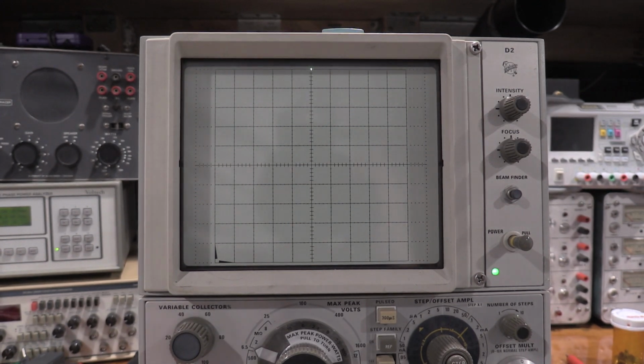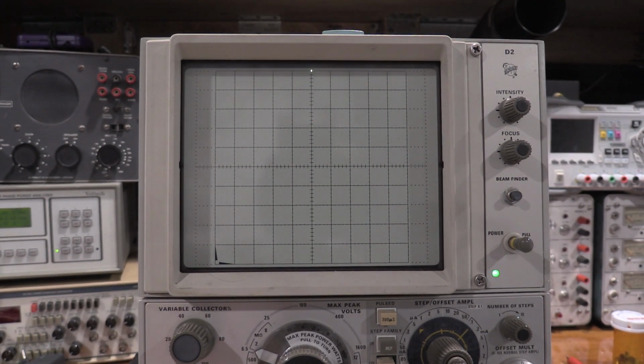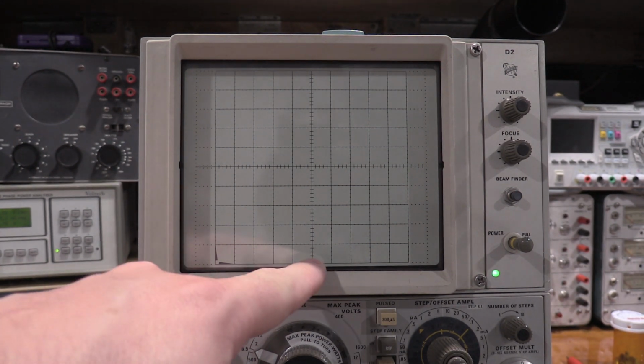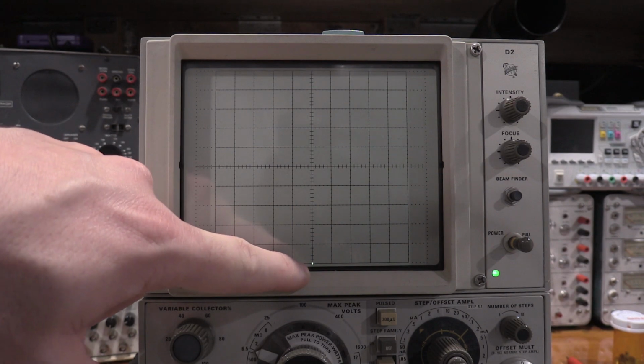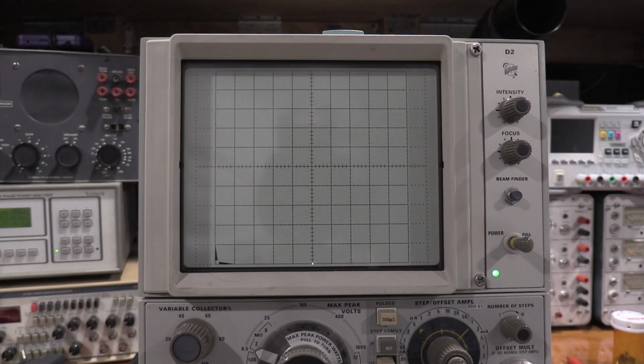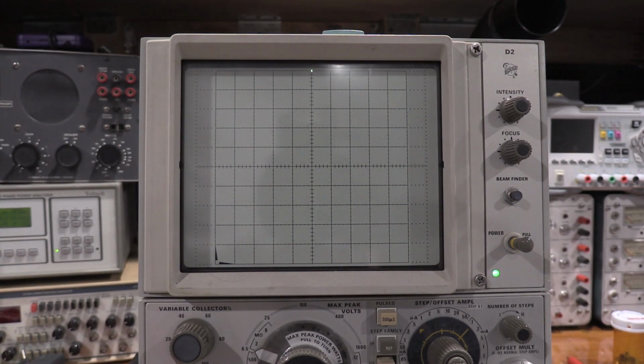Okay, I had to do that a few times. So what they're looking for is when the test fixture is centered, you want it on the bottom line with 4 volts aiding, which I have, 4.001. They want it right on the top line. So this is slightly out of adjustment, not bad, but that's the effect they're looking for right now. So my vertical gain is back into alignment.